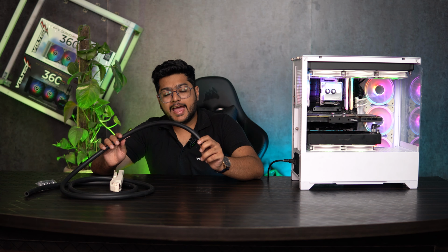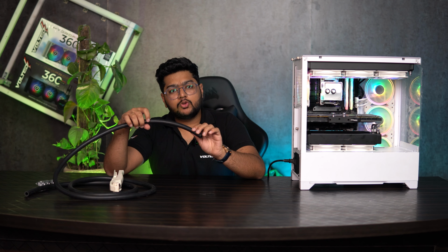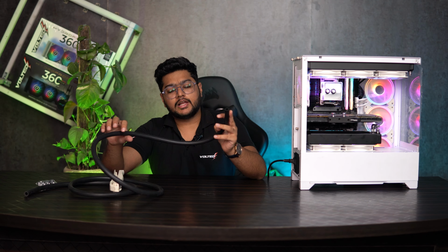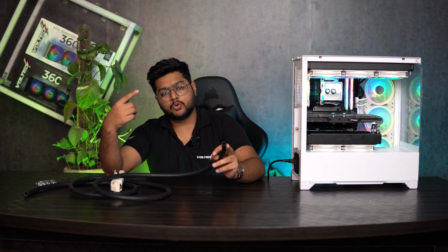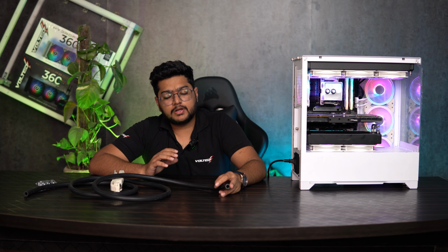The reason we are using black EPDM tubing and not a PVC clear tubing is that PVC clear tubing tends to leave some microplastics into the coolant, which gunks up the pump and eventually your pump will stop. The EPDM tubing has no such microplastics. The life of the liquid will be much more as compared to when you use a clear PVC tubing.